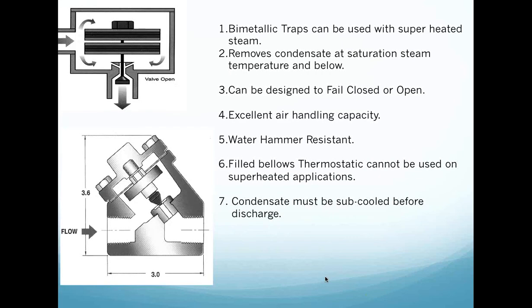We're going to look at thermostatic traps now, and there's two major thermostatic traps that we're going to take a look at. One of them is a bimetallic, the other is a filled element bellows thermostatic. And the filled bellows thermostatic has a N-propyl or isopropyl alcohol fill, so the actual vapor pressure of that fill is different than water. And so these traps follow the saturation curve of steam, but the one thing that they do is that there is many times, based on the way that these traps are built, there will be a subcooling of the condensate before these traps cycle.